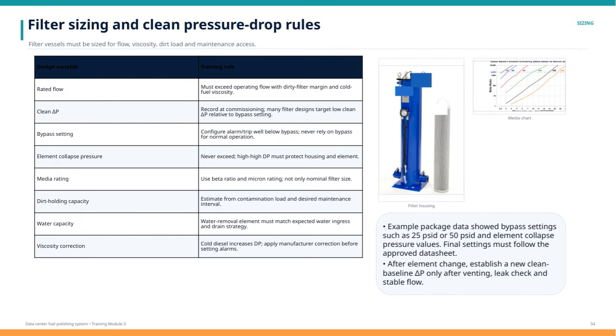Clean pressure drop, or delta P, should be recorded during commissioning. Many filter designs aim for a low clean delta P compared to the bypass setting, helping to optimize efficiency and filter life. Bypass settings are critical for safety and performance. Alarms and trips should be configured well below the bypass pressure to avoid relying on bypass operation under normal conditions. Element collapse pressure must never be exceeded, so high differential pressure sensors should be in place to protect both the housing and filter elements.